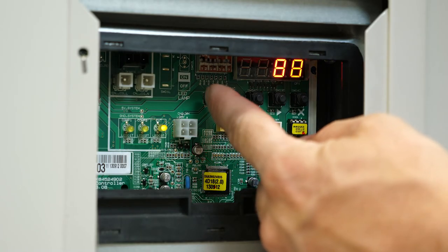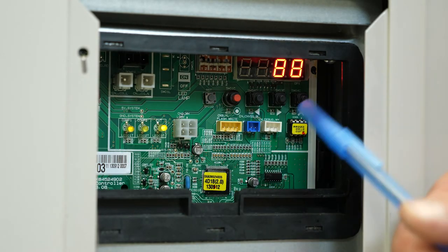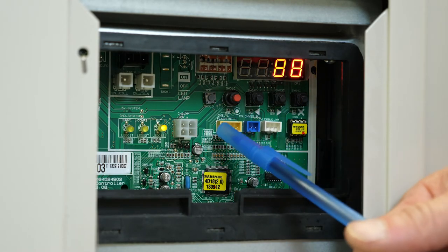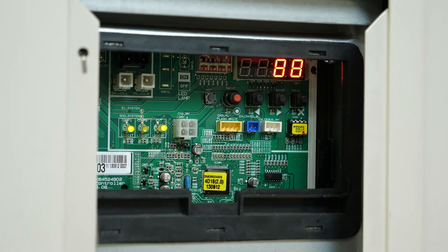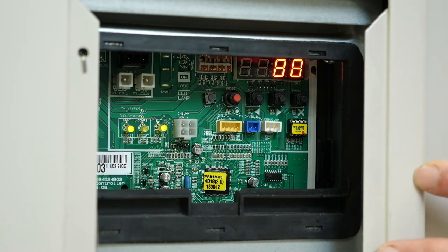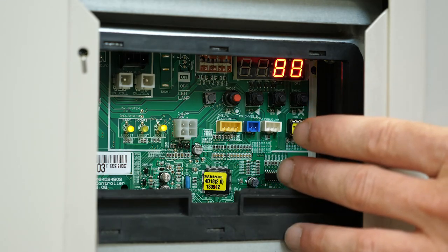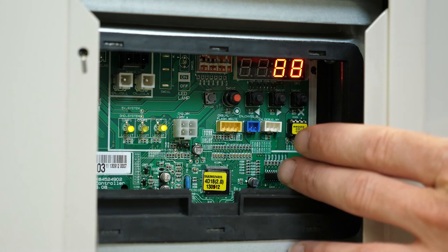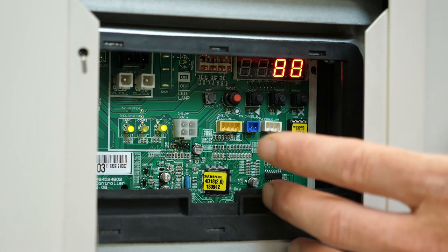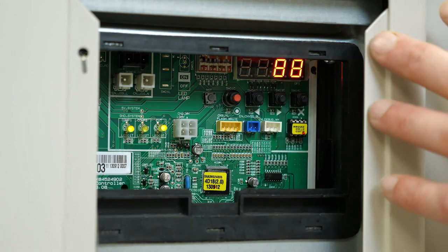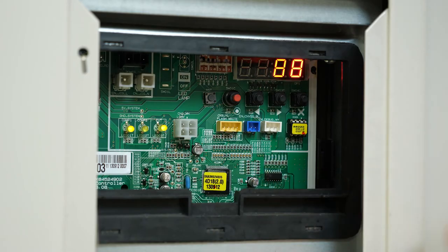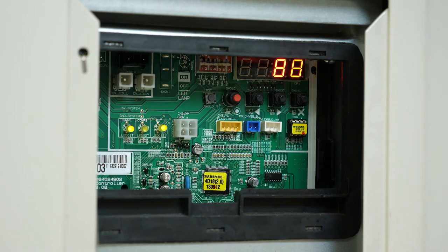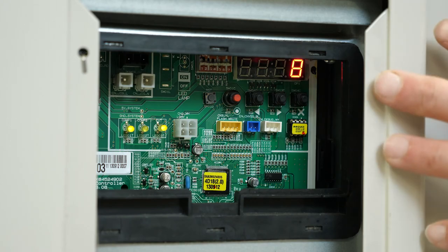Then you'll hit the reset button, the gray button right next to the red button here on the main PC board. The 88 goes off. It'll show you first the indoors, then the HR boxes. On this particular system, those numbers will only be there for about 20 seconds. On the newer product, the multi v5, it'll stay there longer, but on this older generation multi v4, you've got to pay attention.